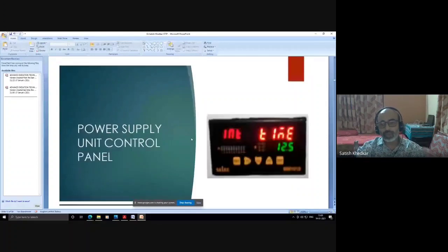Now in this picture you see the control panel is there. In the control panel you see the controls are given. The time is given. That means you can control the sonication time. Then the sonication mode can also be controlled, whether you want continuous sonication or you want pulse sonication. In case of continuous sonication, the sonication probe will vibrate continuously for the stipulated time. Say if you have given a time of 5 minutes for sonication, then the probe will vibrate continuously for 5 minutes and it will stop after 5 minutes have been completed.